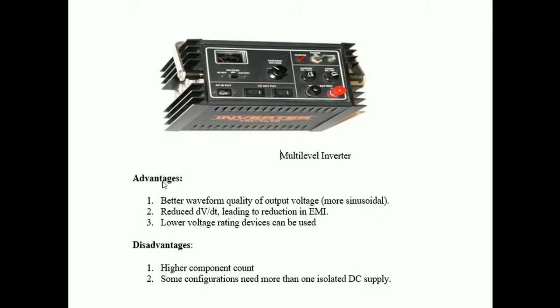The advantages of the multilevel inverter are: better waveform quality of the output voltage — more sinusoidal — reduced dV/dt leading to reduced EMI, and low voltage rating devices can be used, meaning the voltage stress is lesser on different devices. A disadvantage is a high component count, as more components are added, and some configurations need more than one isolated DC source.